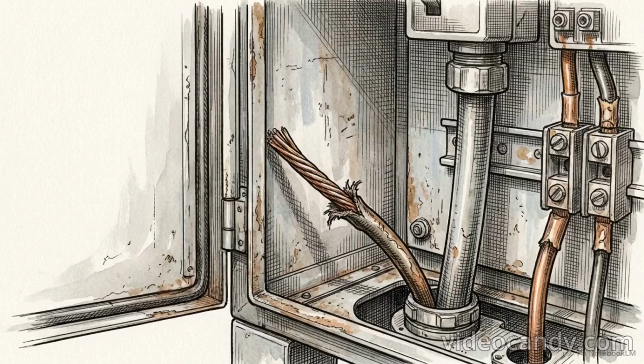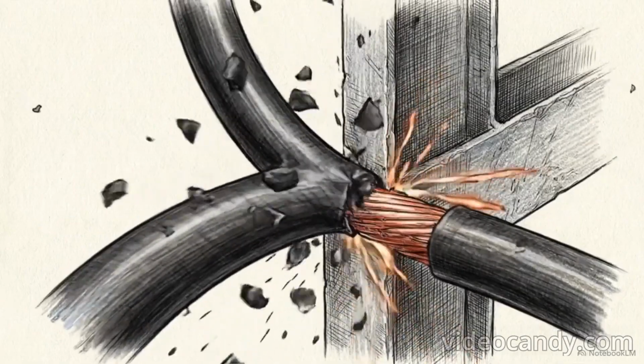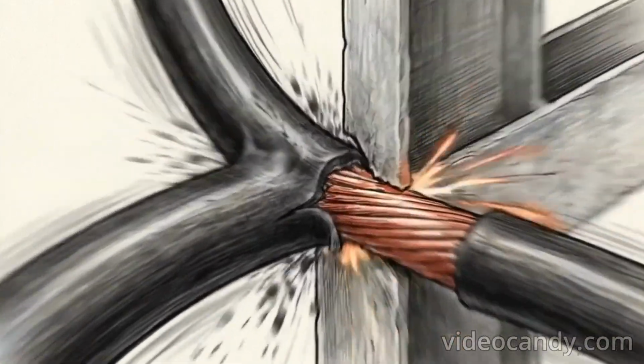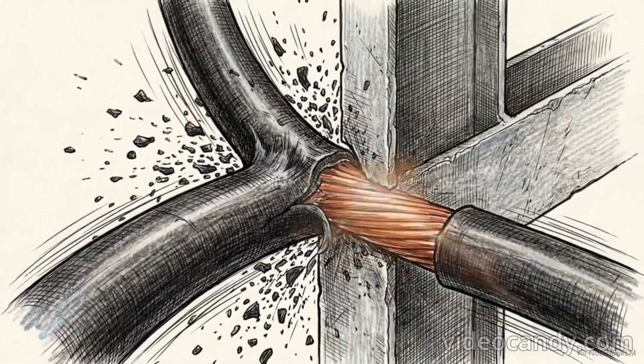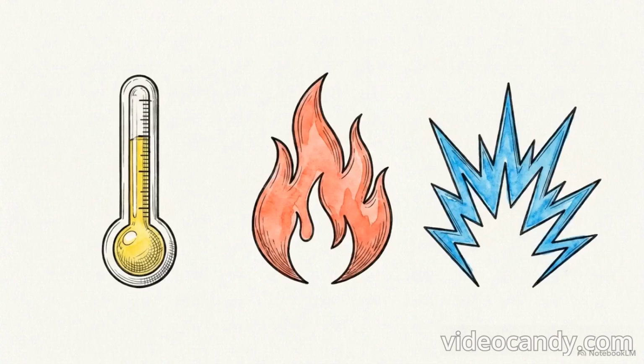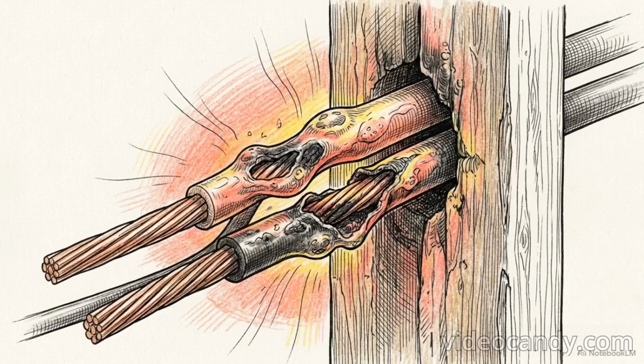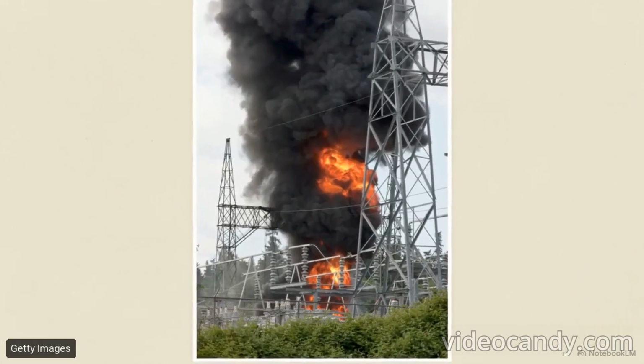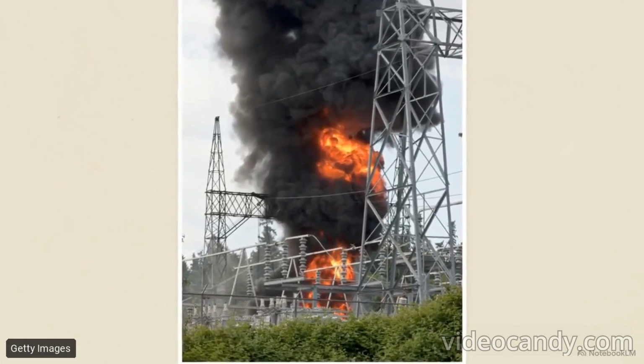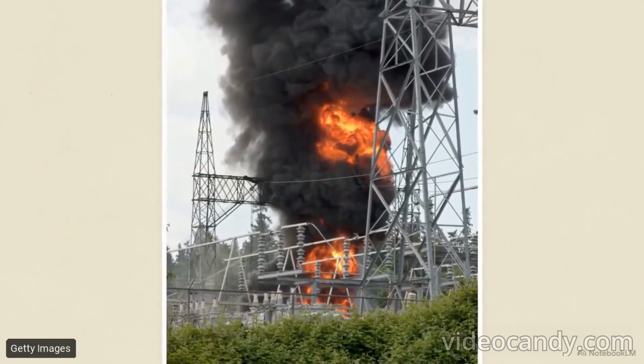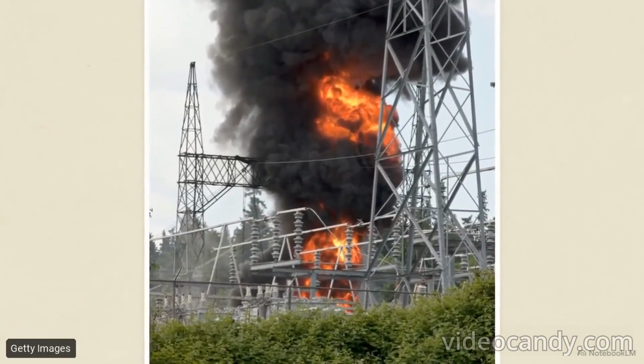Over 95% of real-world failures are unsymmetrical faults. The most common is a line-to-ground leakage, where a single energized phase conductor rubs against a grounded metal chassis or structural beam due to failing insulation. If the hardware fails to clear these faults immediately, the physical consequences scale up rapidly. A sustained overload leads to progressive thermal melting of wire insulation. A dead short circuit releases a massive, instantaneous energy spike, resulting in localized structural tracking fires or explosive arc flashes.